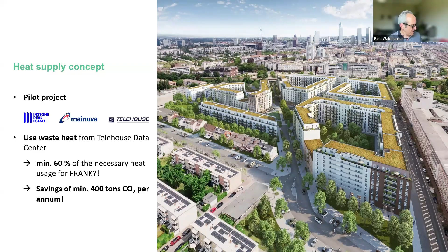The contract itself is for 15 years, and yes, we provide the heat free of charge. The issue at the moment is that our customers use air-cooled servers, so the waste heat temperature is around 30 degrees Celsius, while the flats need temperatures up to 70 degrees Celsius — not just for heating, but also for warm water. The heating load is a maximum of 3 megawatts, maybe a little more, but only in winter when it's very cold — around -10 to -12 degrees Celsius, which we don't have very often in Frankfurt. That might happen only a few days every few years.